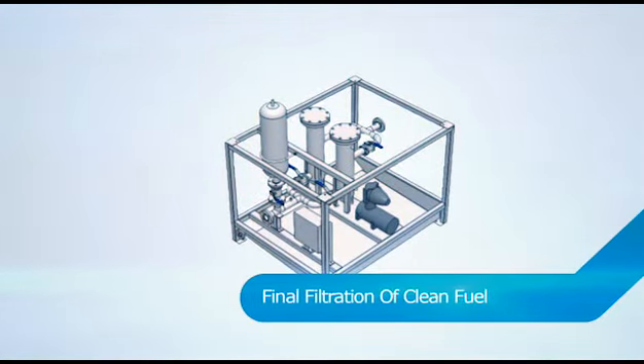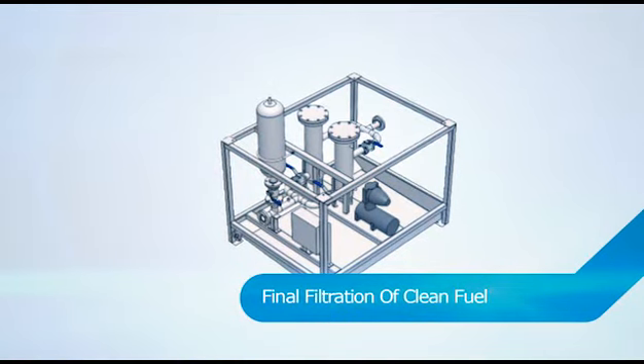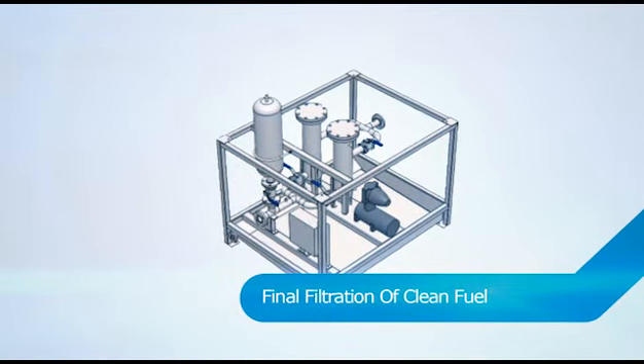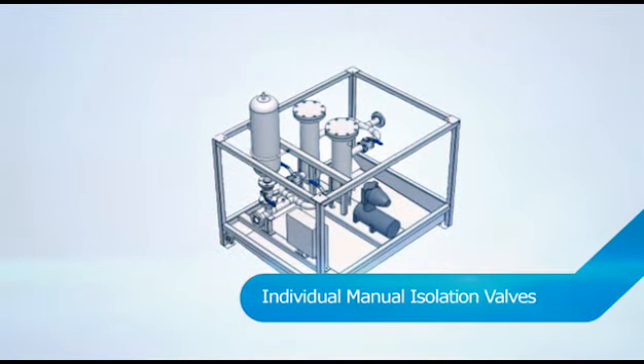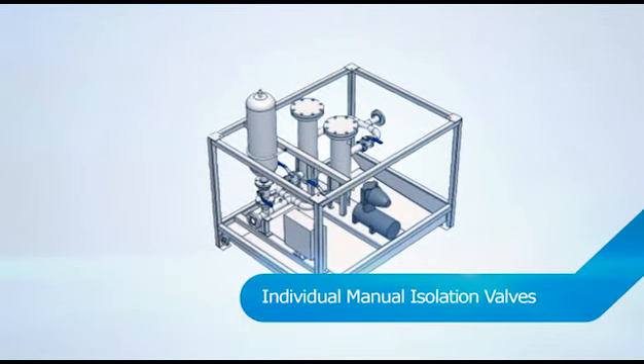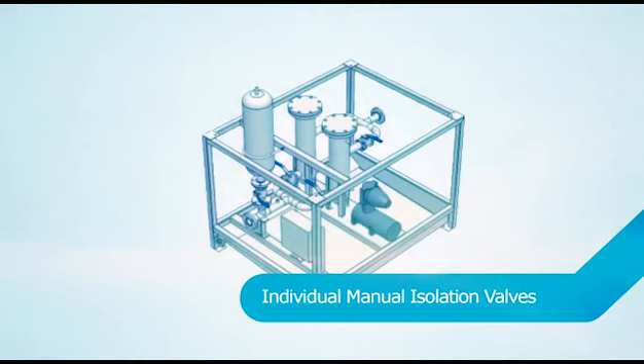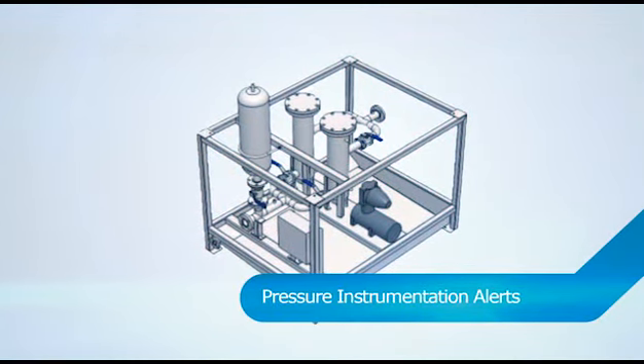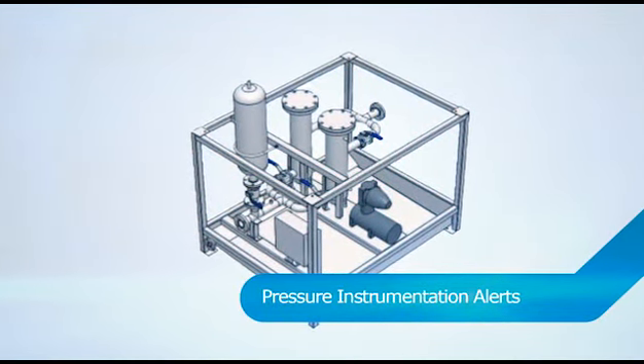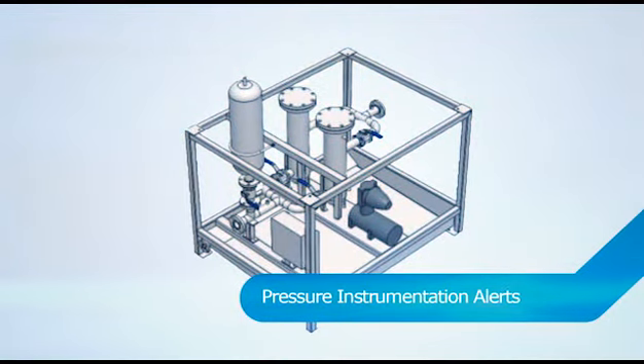The last chance filters are located at the turbines to provide final filtration of clean fuel. The filters are a duplex configuration with individual manual isolation valves. Upstream and downstream pressure instrumentation alerts the operators when a filter is blocked.